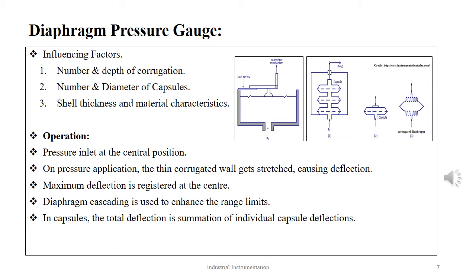The unknown pressure is introduced in the central position of the capsule or diaphragm. The pressure tends to push the thin walls of the corrugated device outward, causing deflection in the equipment. The maximum deflection is reported at the central position. The total diaphragm deflection is the summation of all the individual deflections recorded by each of the corrugations or the capsules. The deflection is observed on a pointer scale set up by a gearbox arrangement.